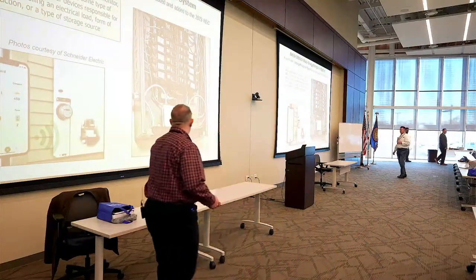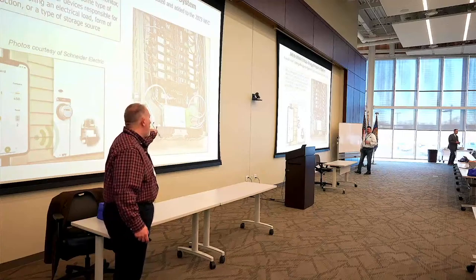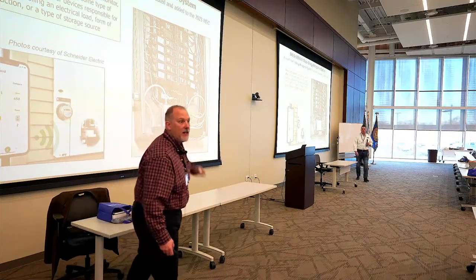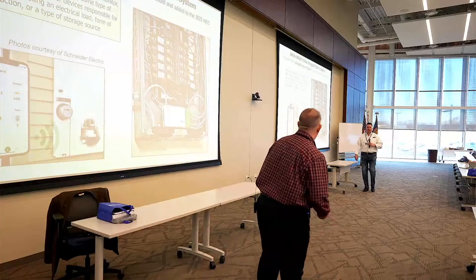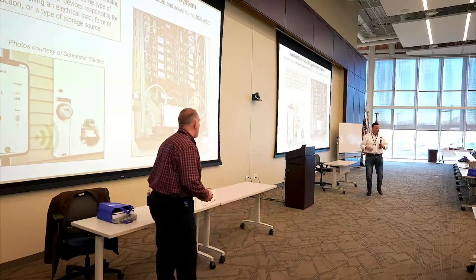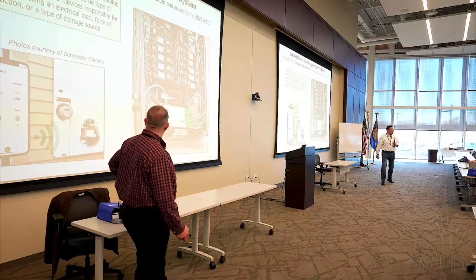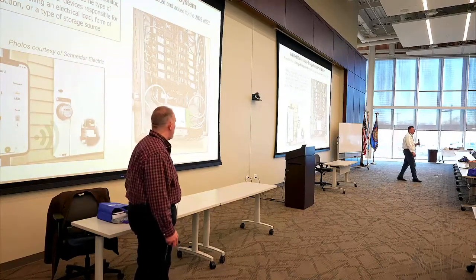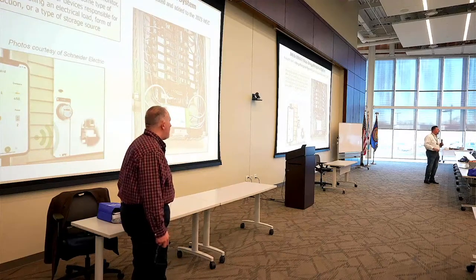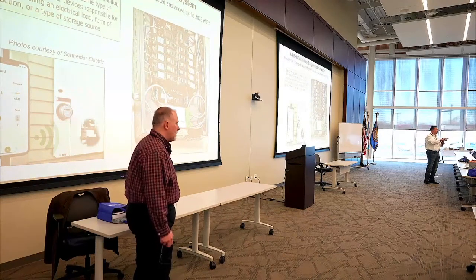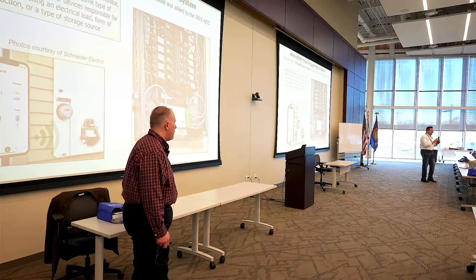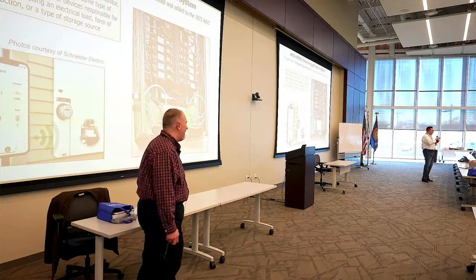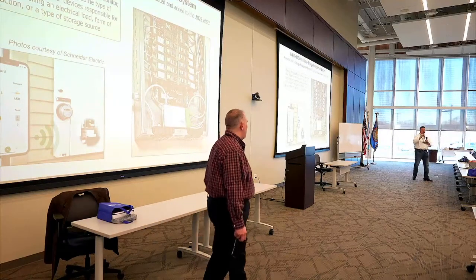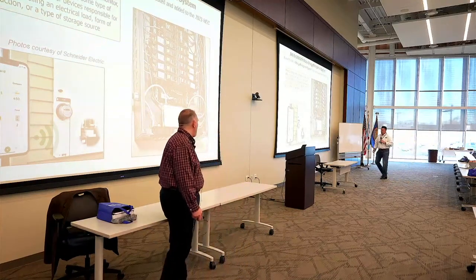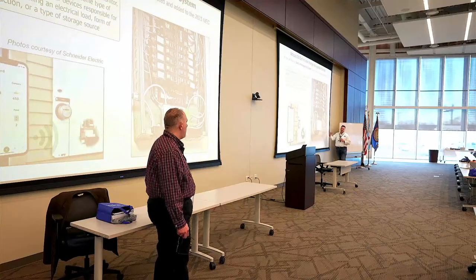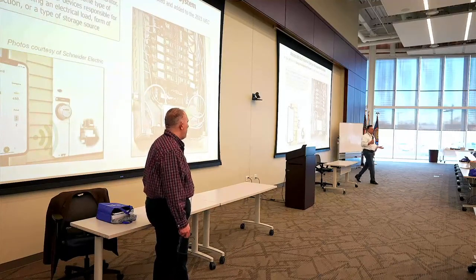We're seeing a lot of these. And you remember in 408, we have restrictions on what can be placed inside of panel boards. 312 too, right? Cabinets also - 312.8 has that too. And they actually added language to clarify that, because that's one of the things I get questions about a lot. Can we put things in panels? What can be in a panel? How much space do I need? We can't put a low voltage transformer in a panel, even though I've seen that in condos. But what can I put in the cabinet? The panel board goes inside the cabinet. So in 312, we're looking for what can be allowed in that space. They did put some language specifically mentioning energy management, but you will see energy management equipment inside the cabinet where your panel board is, that we call a service or a panel.